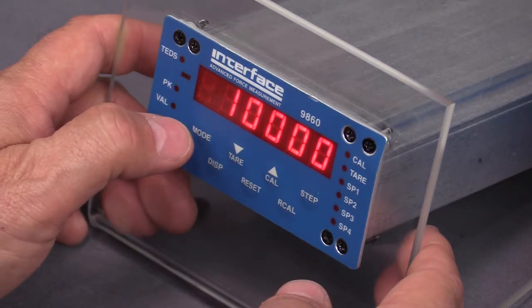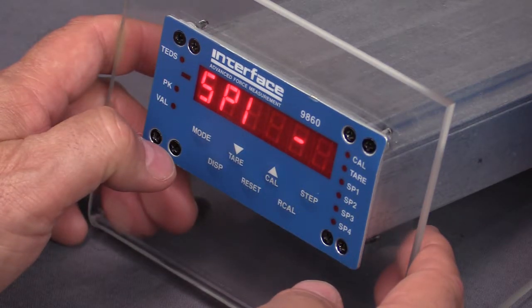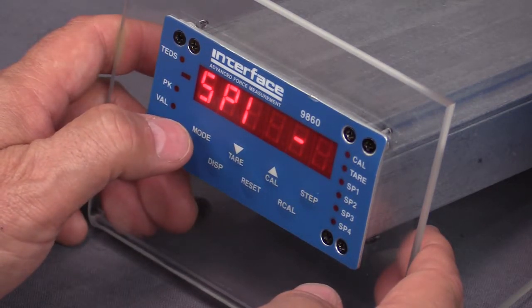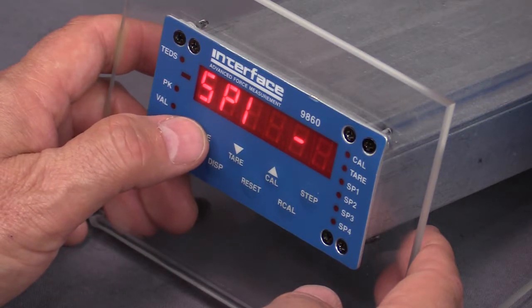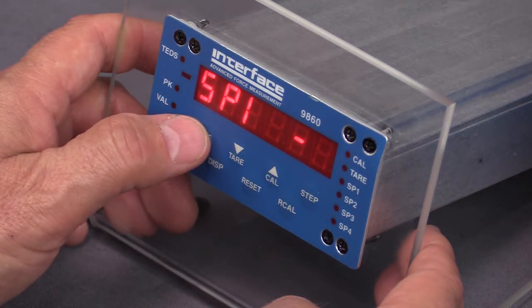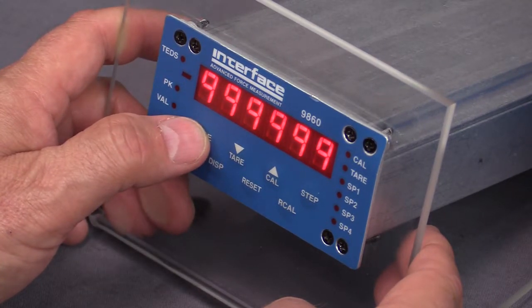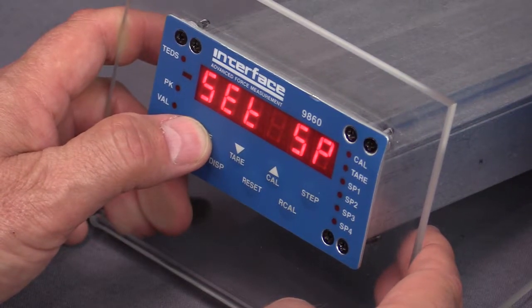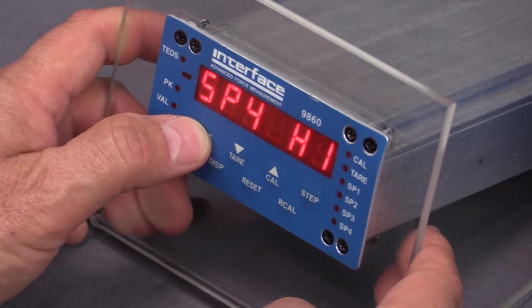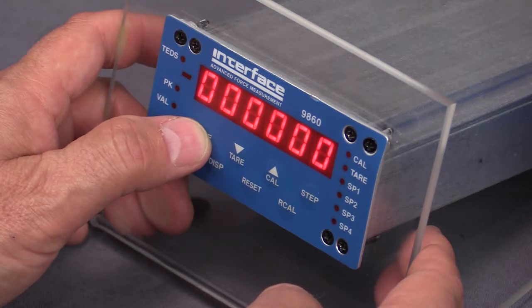Hit the mode button again. Now these are for a series of different set points. We're not going to go through that right now, but this indicator has open collectors so it can trigger relays based on whatever value is set inside of this indicator. So again, you can read the manual to set these if you need them. I'm just going to keep advancing all the way through. There's four different set points, then there'll be a hysteresis value which again has to do with set points.